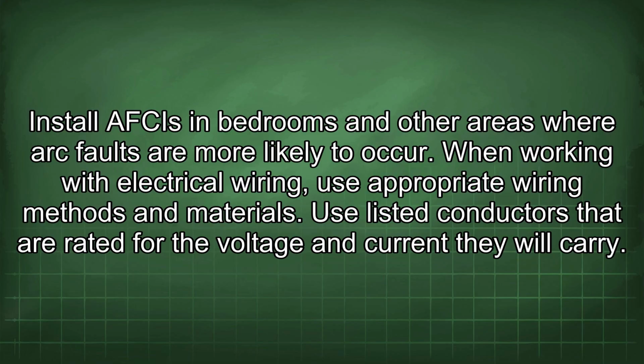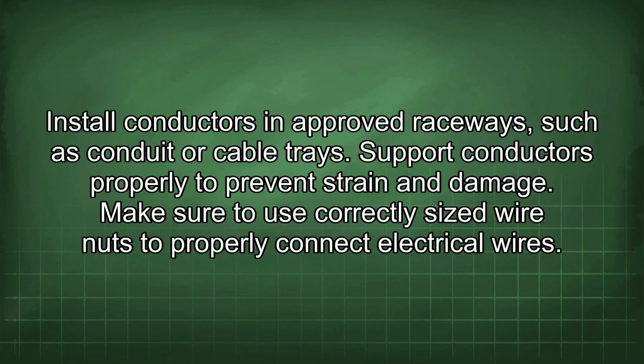When working with electrical wiring, use appropriate wiring methods and materials. Use listed conductors that are rated for the voltage and current they will carry. Install conductors in approved raceways, such as conduit or cable trays. Support conductors properly to prevent strain and damage. Make sure to use correctly sized wire nuts to properly connect electrical wires.